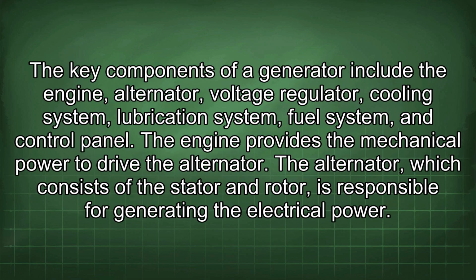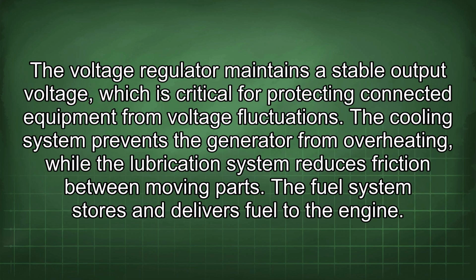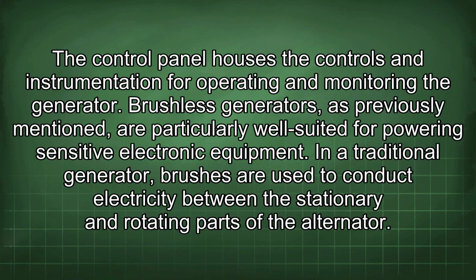The key components of a generator include the engine, alternator, voltage regulator, cooling system, lubrication system, fuel system, and control panel. The engine provides the mechanical power to drive the alternator. The alternator, which consists of the stator and rotor, is responsible for generating the electrical power. A voltage regulator maintains a stable output voltage, which is critical for protecting connected equipment from voltage fluctuations. The cooling system prevents the generator from overheating, while the lubrication system reduces friction between moving parts. The fuel system stores and delivers fuel to the engine. The control panel houses the controls and instrumentation for operating and monitoring the generator.